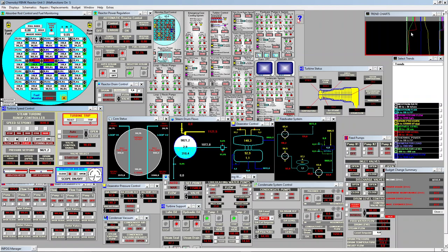You see, reactor level increases when you increase flow. This is because you are reducing pressure in the drum. When you reduce pressure, two things happen. One is that the volume of the reactor content expands because it's partially gas, because there is a boiling within the reactor. And second is that the boiling itself increases its rate, because at equal heat from the fuel and lower pressure, you will have more boiling. So that's why you have a reactor level increase, and you don't want to increase too much, because if it spills over the exit of the drum, you could send liquid water to the turbine and that would break the turbine.